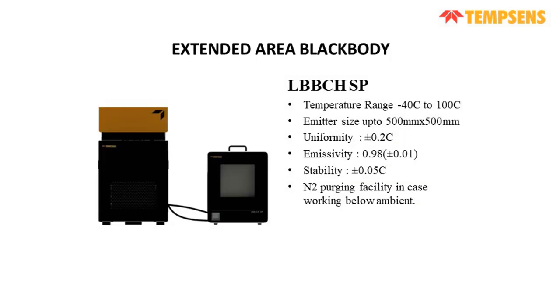So for the lowest range, -40 to 100 degrees centigrade, we have LBB-CH-SP. The emitter size can be up to 500 mm by 500 mm, and the uniformity for this model is plus minus 0.2 degrees centigrade. It comes with a chiller unit that continuously chills it. The right side is the black body head, and on the left side we have the chiller unit, a circulating chiller which cools it down to -40 degrees centigrade.